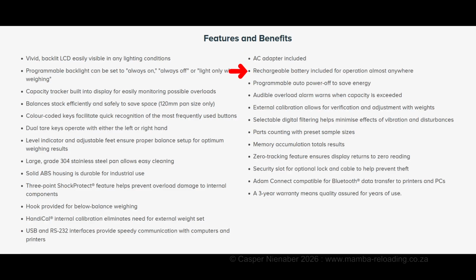A rechargeable battery, which can last up to 24 hours, is included for operation almost anywhere. This is particularly useful for load development at the range, where mains power isn't available. Programmable auto power off to save energy. An audible overload alarm warns when capacity is exceeded. External calibration allows for verification and adjustment with test weights. Selectable digital filtering helps minimize effects of vibration and disturbances.